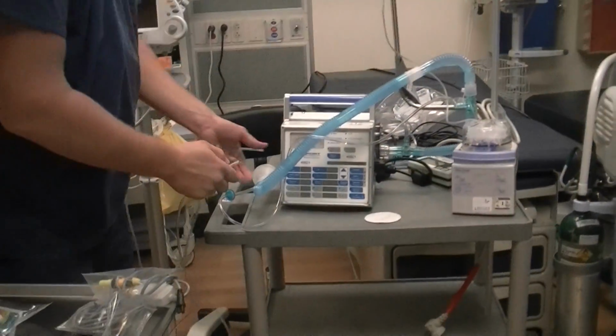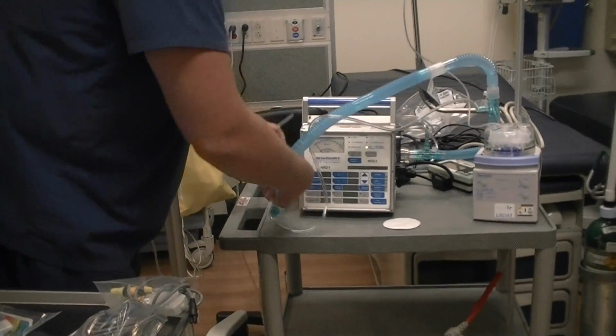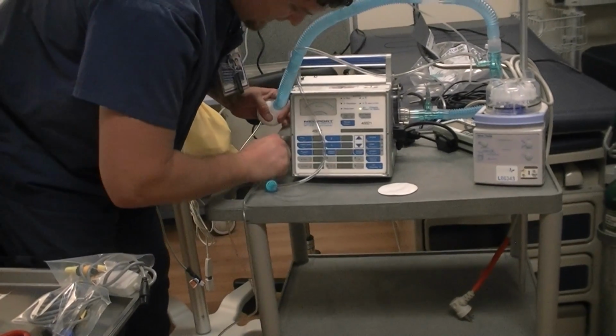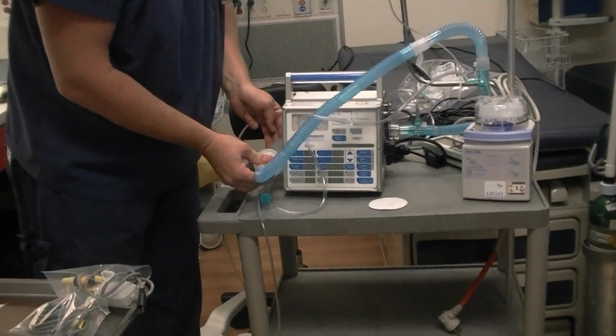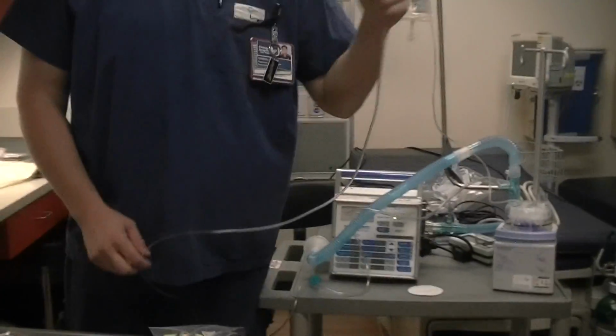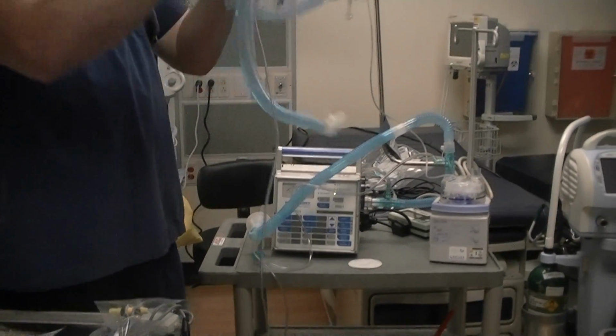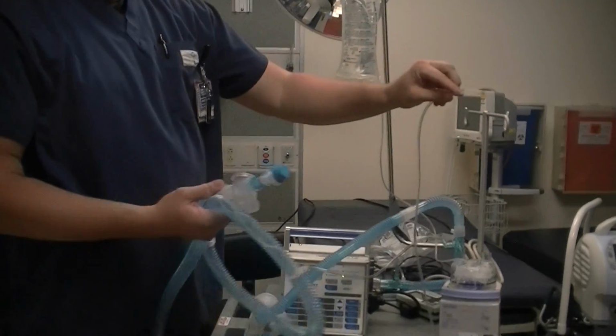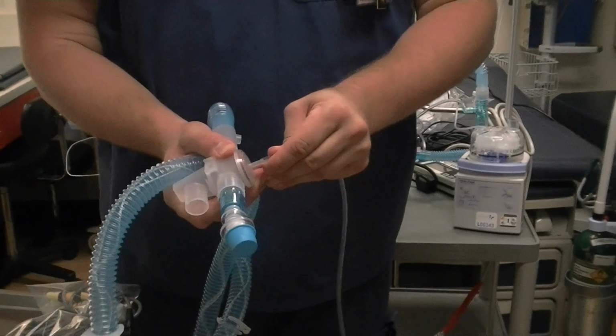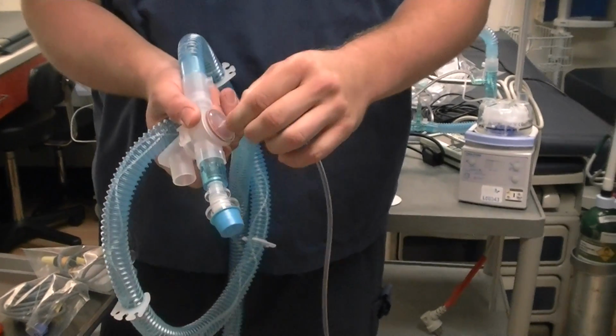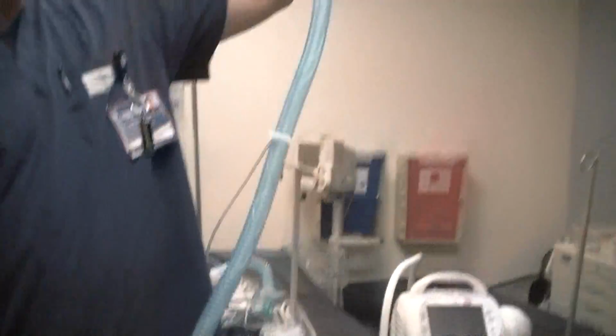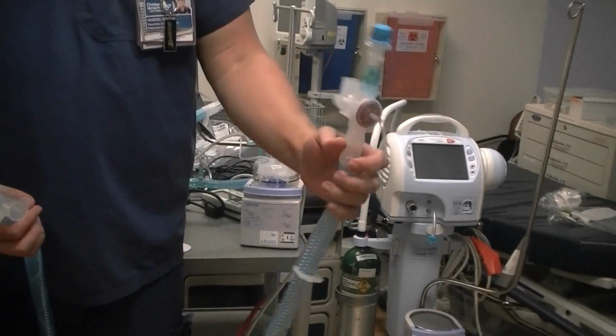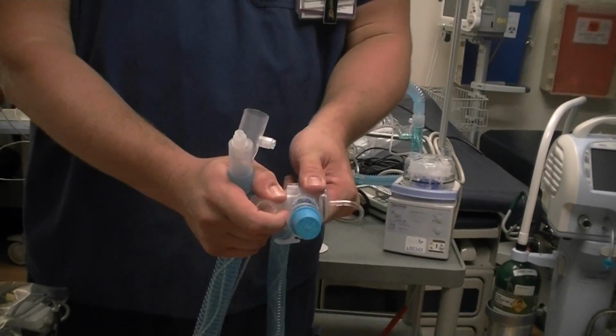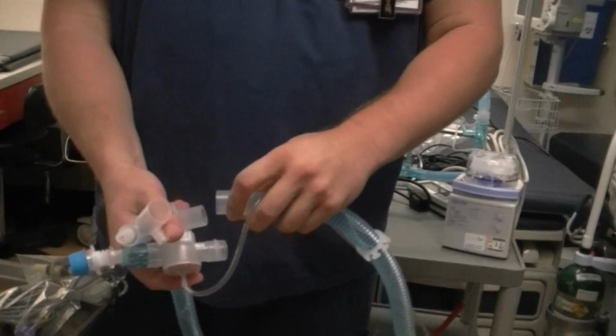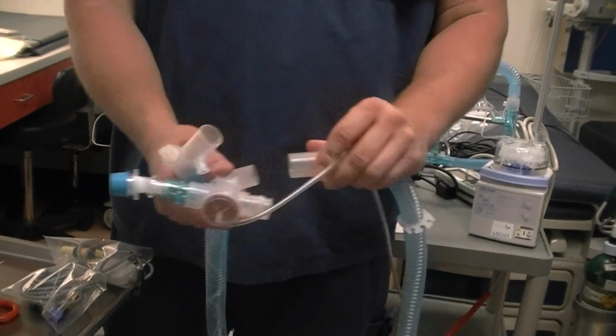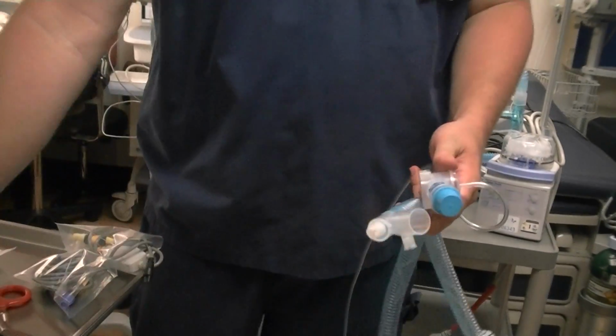And that's the cut. You're going to remove your bacteria filter from here and hook it up to your exhalation side. Push it in there as deep as you can, because this line itself tends to dislodge and goes unnoticed, and people sit there for a while trying to figure out what's going on. You're going to grab your exhalation line and hook it up to your exhalation valve. I'd recommend you don't put too much pressure on this because these do tend to break sometimes. And you're hooked up to your exhalation side. I recommend that this piece come off, only because we did have an incident where somebody connected the ventilator like that. So you can just pop this off and throw it away.